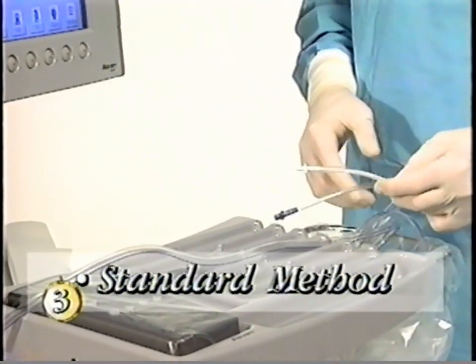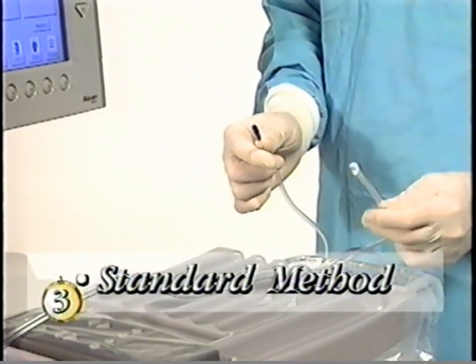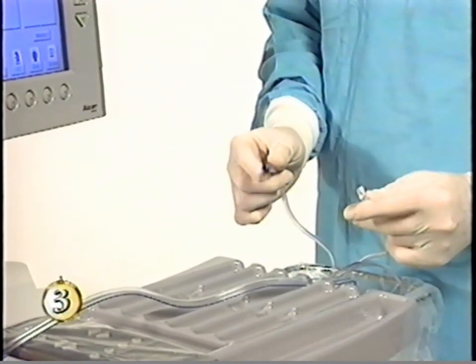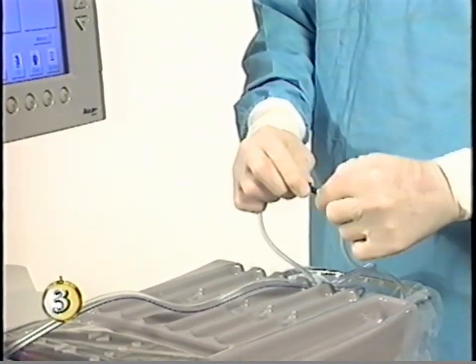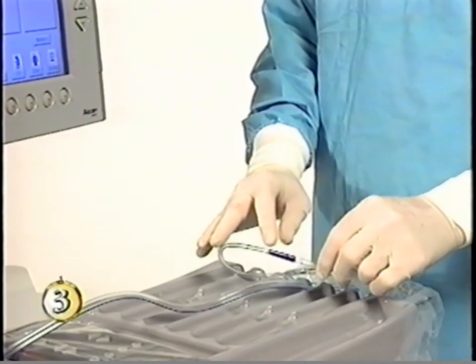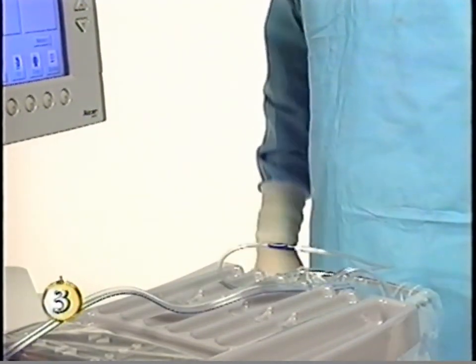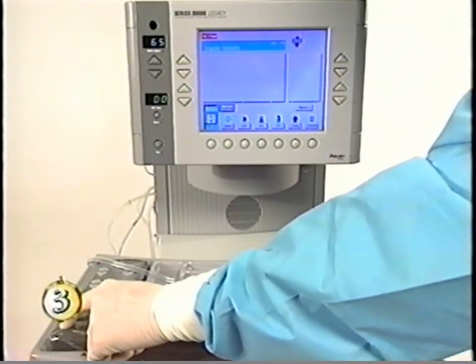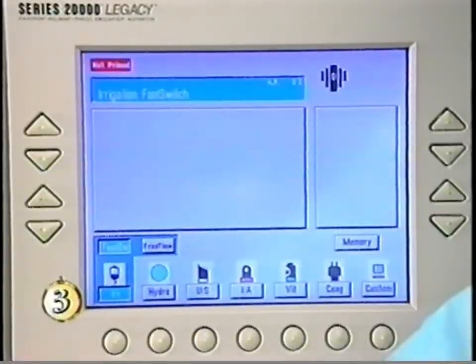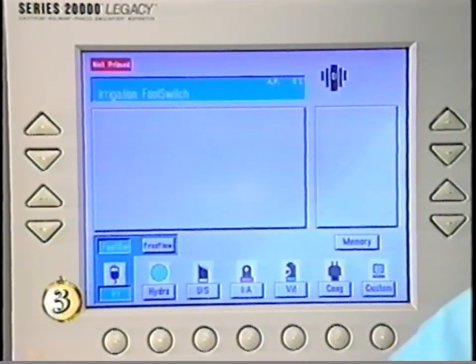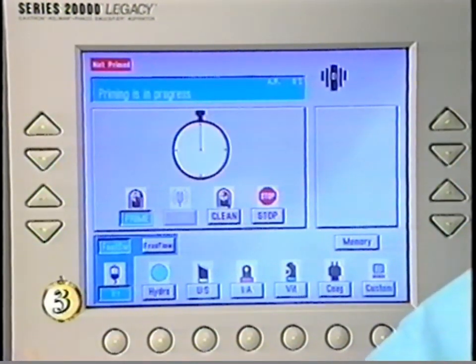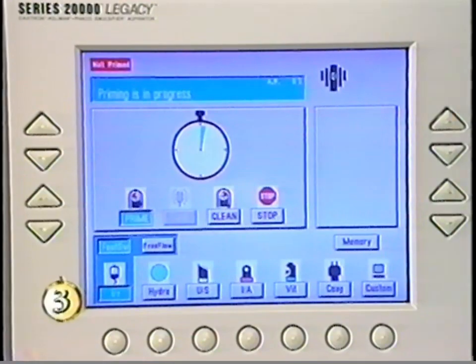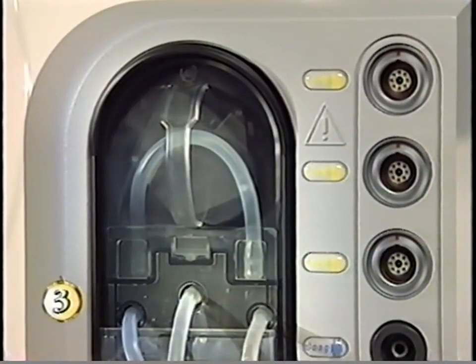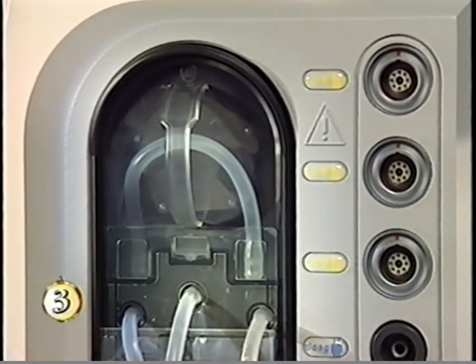Begin the system fluidics test by connecting the blue luer aspiration line and white luer irrigation line together. Be sure to connect lines completely to prevent air from entering the aspiration line. Select Irrigation FastSwitch mode. Press Test to enter the test menu. Then press either Prime on the front panel or press Test again to initiate the prime sequence. The IV pole will raise to its maximum height. The 3 test phases will take about 2 minutes.